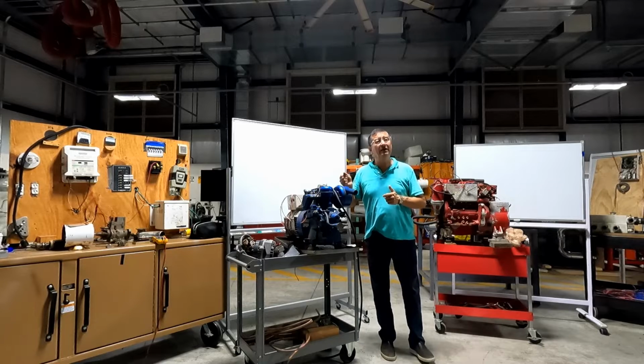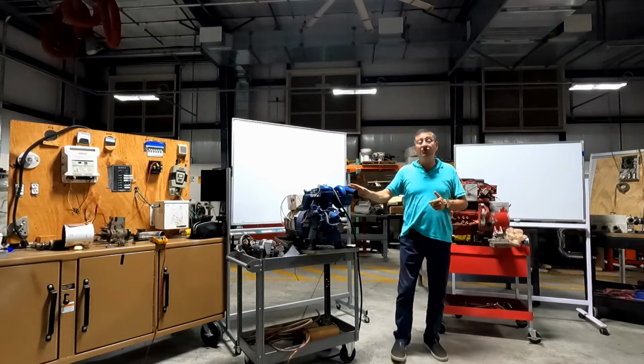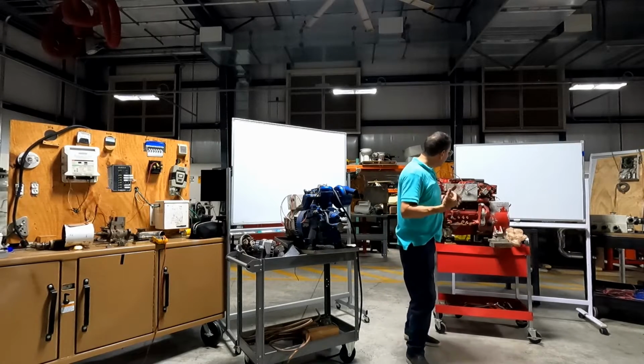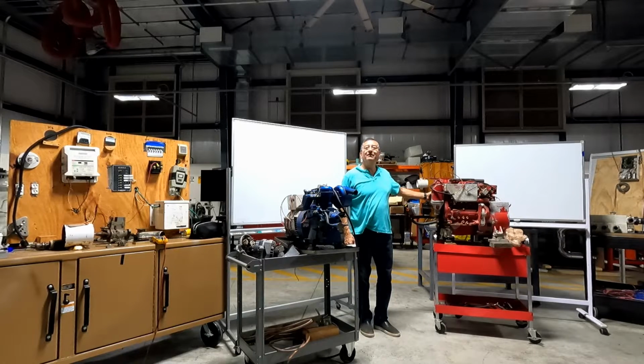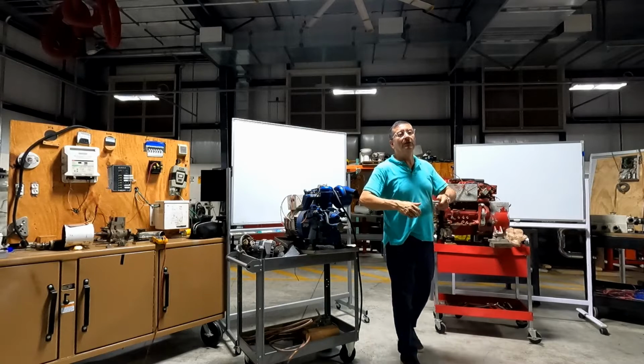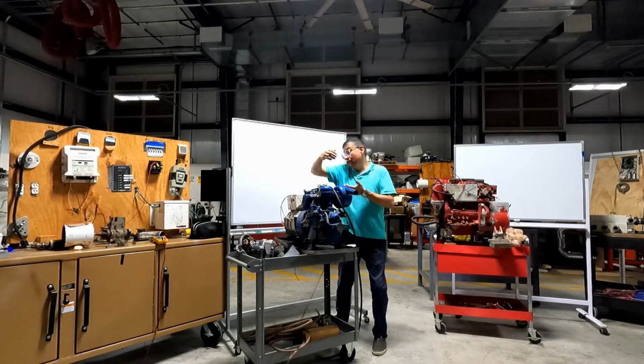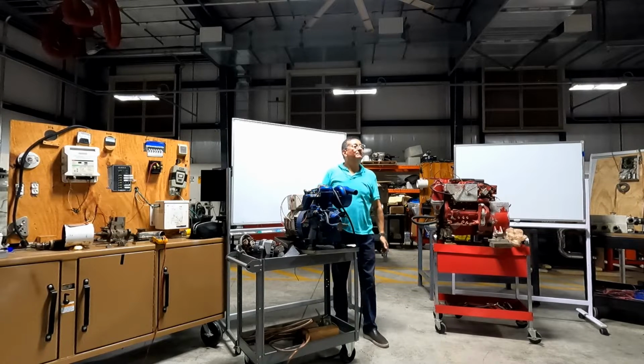What type of batteries is recommended for this? Cranking batteries, because the battery is used only to crank the engine. It is exclusive to start. After that, the generator continues running, producing your own DC power with the alternator of the engine, and of course the AC with the back end.